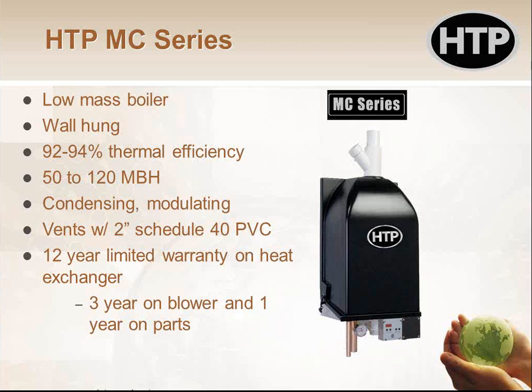This is a fully modulating boiler. This particular one has a 3-to-1 turn down, which means it goes from 33% up to 100% firing rate. It's not a very good turn down, but this is an entry-level boiler here. It's Schedule 40 PVC, 2-inch. And most residential boilers have a 10 or 12-year warranty. The HTP ones all have 12-year, limited on the heat exchanger, 3-year on the blower, 1 year on the parts.